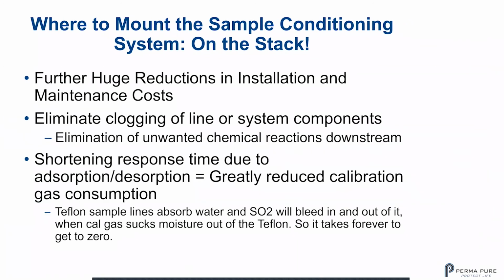Further, huge reductions in installation and maintenance costs come from the elimination of anything that will clog the line or system components. We eliminate unwanted chemical reactions downstream of the sample system, so we never have the potential of stuff gumming up in the sample lines. As you might well know, sample lines are not the most reliable systems in the world, and a lot of times the reason why you get clogging is because somewhere along the line, the heated line fails, and it doesn't heat all the way through.